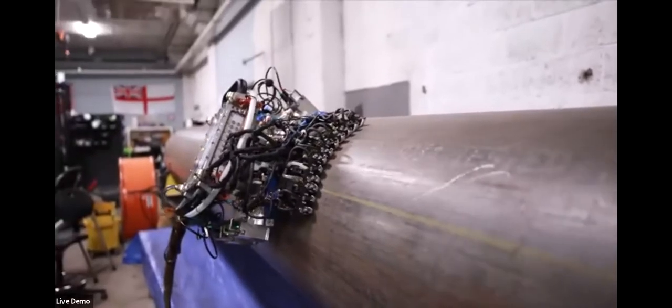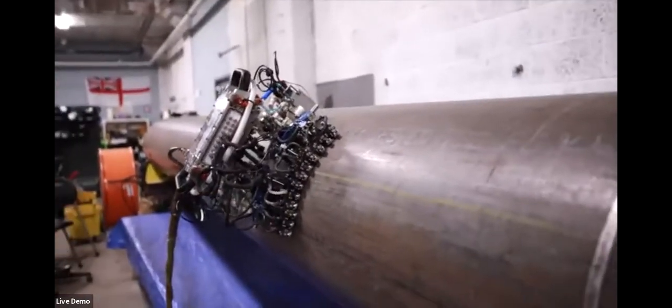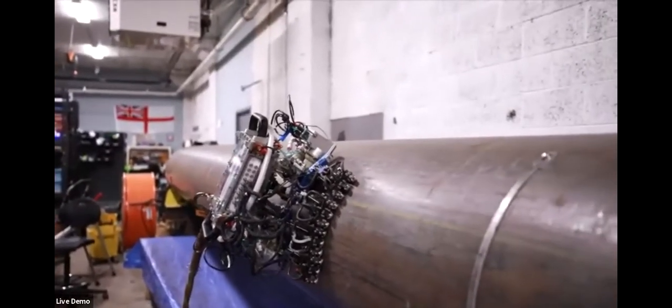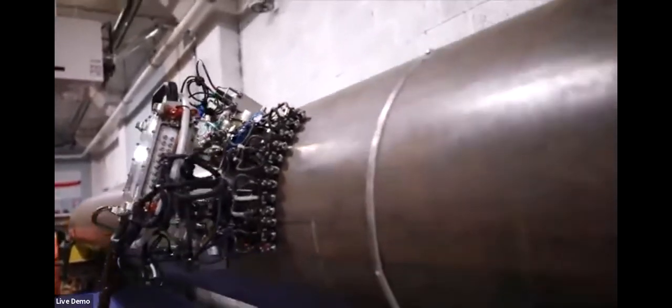So this particular robot, no matter what size pipe it is on, the suspension will ensure that as long as 10 inches is provided between scaffolding or any other obstacle above the system, you'll be able to climb under that and be able to continuously collect data.